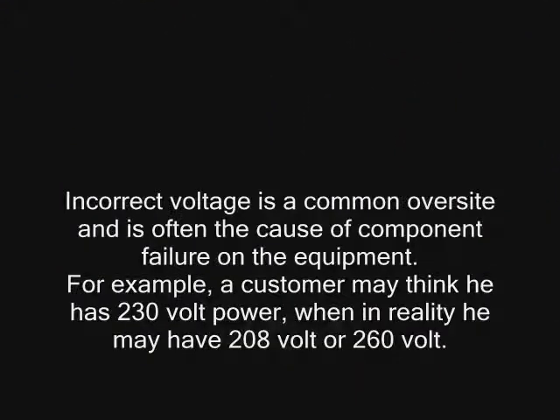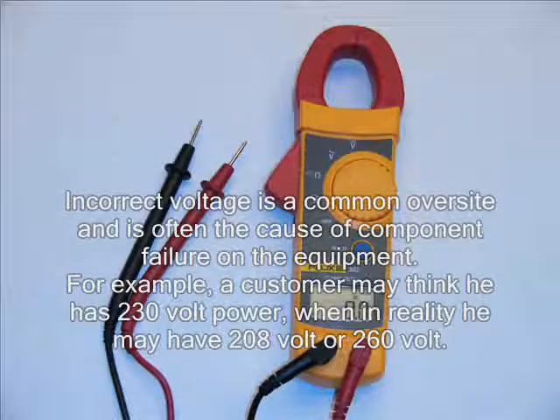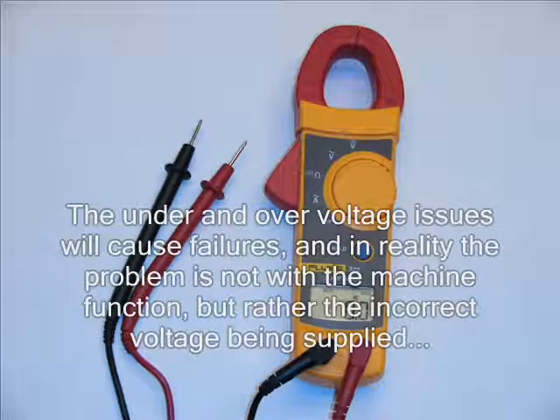Incorrect voltage is a common oversight and is often the cause of component failure on the equipment. For example, a customer may think he has a 230 volt power when in reality he may have 208 volt or 260 volt. The under and over voltage issues will cause failures, and in reality the problem is not with the machine function, but rather the incorrect voltage being supplied.